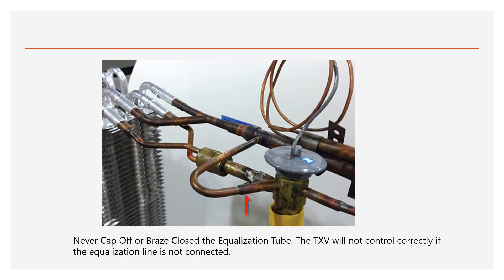Never cap off or braze closed an equalization line. The TXV will not control correctly if the equalization line is not connected.